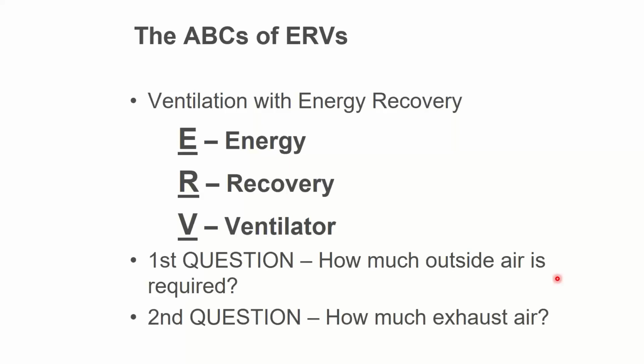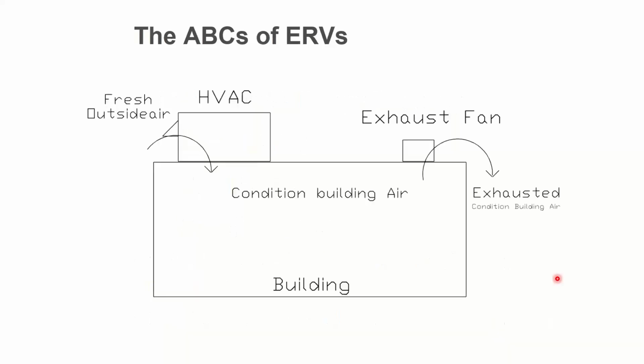The next question is how much exhaust air do you got? Because what's going to happen is I'm going to reclaim the energy from your exhaust air, and I'm going to transfer that energy, not the dirty air, but the energy, to the outside air. If you don't have a lot of exhaust air, it's going to be hard for me to find the energy. And if you don't have a lot of outside air, financially, why am I buying this? Like, you only need 100 CFM? Not super interesting to me. Oh, you got 1,500? Oh, you got 10,000 CFM of outside air? Oh, okay. Now it's super interesting from a financial standpoint.